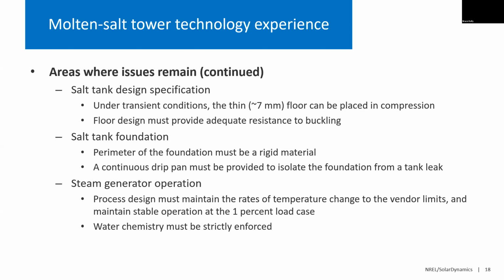In terms of the steam generator, this has presented some problems at a number of plants. The vendor will typically provide an allowable rate of temperature change, let's say 10 degrees a minute. It's important to stay within that limit. The heat exchangers do not have an infinite fatigue life if they have a rate of temperature change of 10 degrees a minute. And if you start to exceed that, then the fatigue life drops by a lot. And two effects. One, you can develop a failure of the heat exchanger itself, but also two, you can start to relax the friction connection between the tubes and the tube sheets if you try to operate with high rates of temperature change. And when that happens, then you develop a leak in the heat exchanger. That can be fixed by tube plugging, of course, but the downtime to do that is at least a week. And it doesn't take very many failures over the course of a year to cause the availability of the steam generation system to suffer by quite a bit.